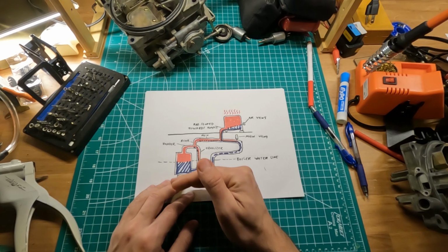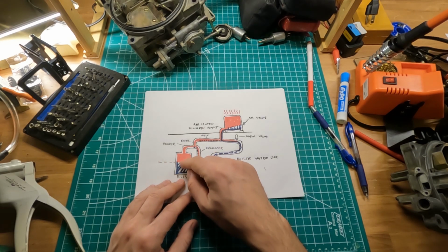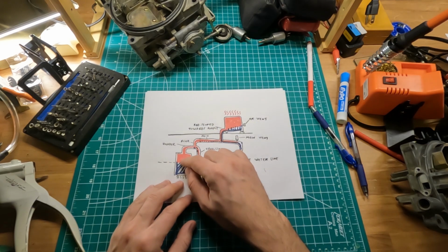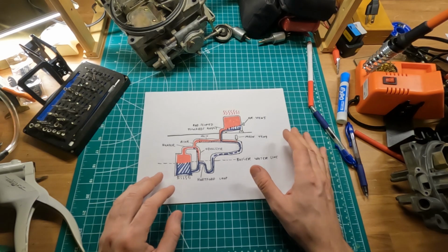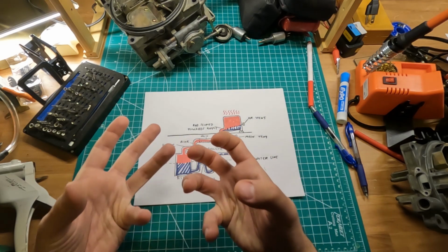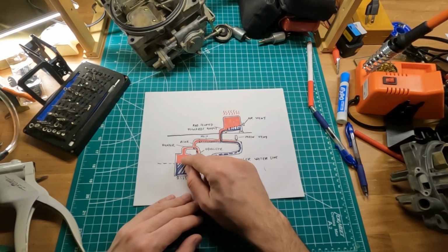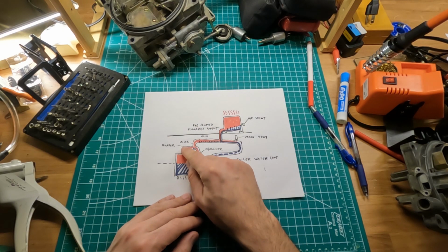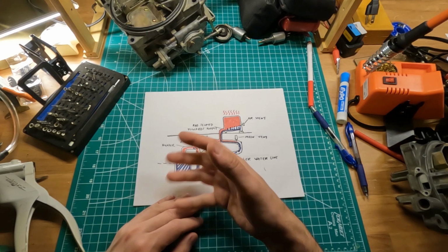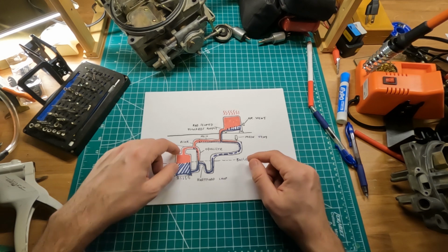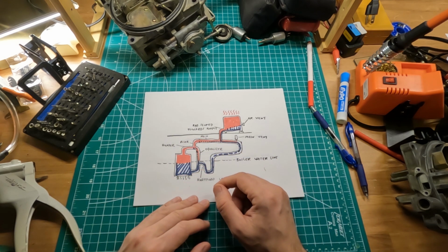This water level right here goes quite violently up and down, and because of that, some wet steam can be sent up the header into right here. It's actually quite amazing when you watch some videos of how much force the surface of the water has when it releases steam. So some of that water goes up the header and touches the first cold pipes, and later on, when they warm up, with all the turns and twists, it releases some of its velocity.